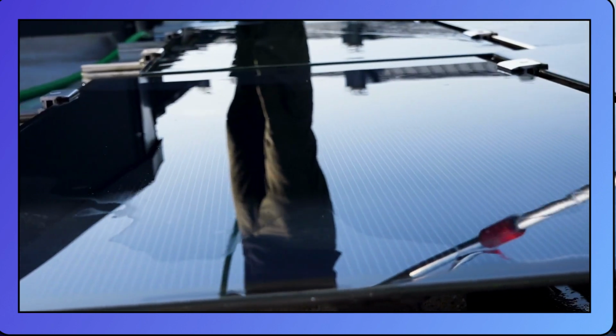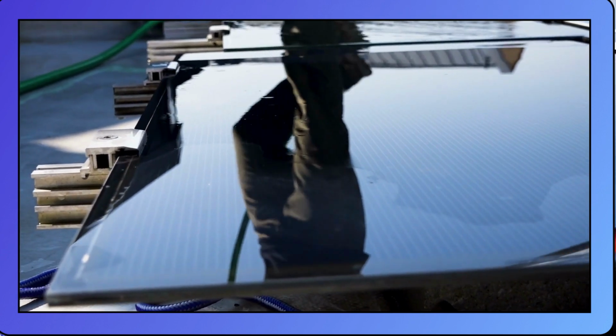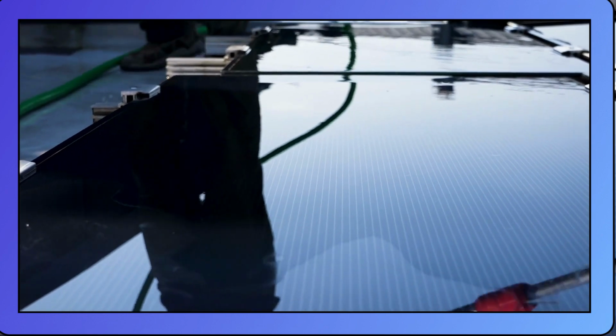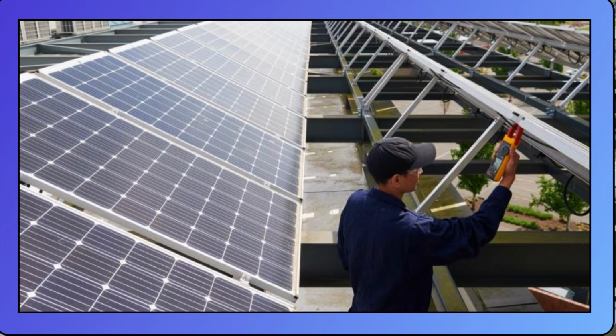You may get a photovoltaic system going safely and reliably and maintain it running safely and reliably by being aware of potential issues, testing, and troubleshooting with tools appropriate for the task at hand. The PV panels, load, inverter, and combiner boxes are the four components of a PV system that are often the focus of troubleshooting. Draw a diagram of each branch's wiring going backward from the combiner box.